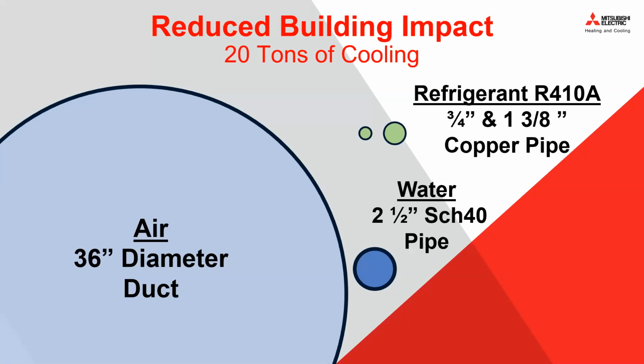Now, when we're talking about thermal energy and moving it around the space, there's no more efficient way of transporting thermal energy than refrigerant. These circles represent the amount of space that you would need to move air with the same amount of energy. So here we have 20 tons of cooling energy. You need a 3-foot diameter duct. For water, you need a 2.5-inch pipe. And when you get down to refrigerant, between your suction and your return, you have 3/4 and 1 3/8 pipe.